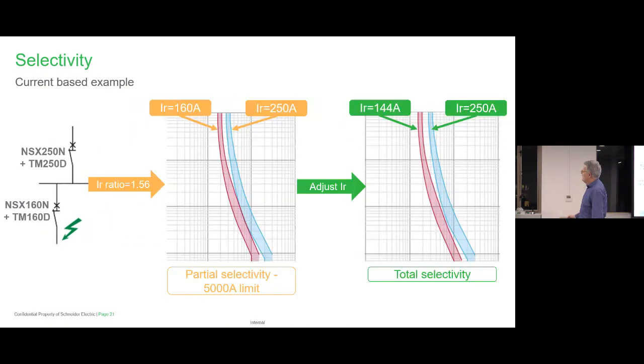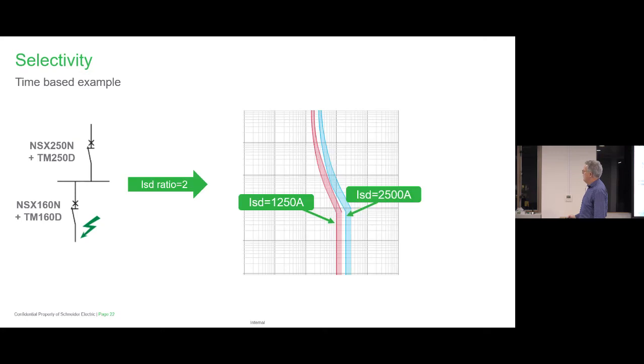So I'll just go back there. This was current based. So it's the thermal part of the curve we're looking at here. Now we're going to look at the time based, which is this part of the curve here. So these are TMD trips. They're not electronic trips. They were the base level breakers, which you'd see everywhere. And you can see here it's 1250 amps ISD, and it's 2500 amps here. And I'll go back, and that's actually giving us total between these two, because that is 2 times. Remember we said 2 times?